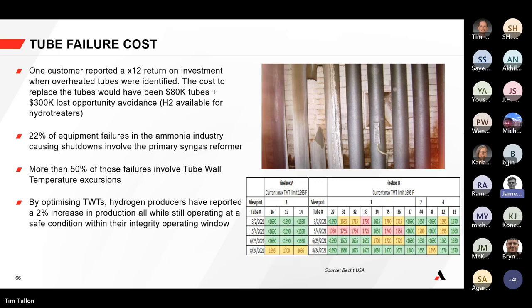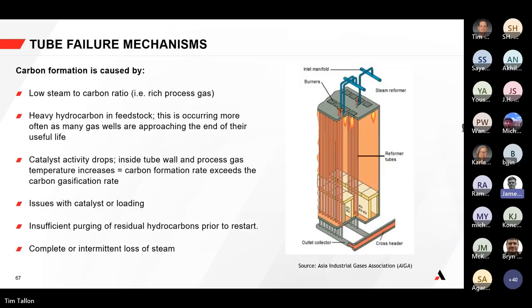Cross-referencing research from the ammonia industry, one research group called Ammonia Know-How informed us that 22% of equipment failures in that entire industry involved the primary syngas reformer, and more than half of those failures involved tube wall temperature excursions. A lot of those occurred during startup, cutouts, or upsets — so it's not just about continuous accuracy; it's also about coping with upsets to the process. Getting this right can produce a big increase in production while still operating safely.